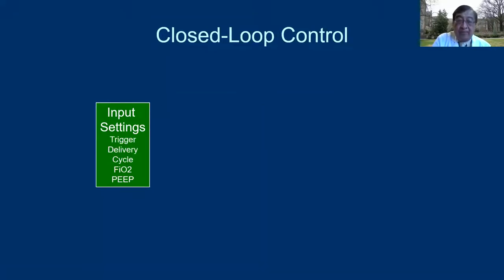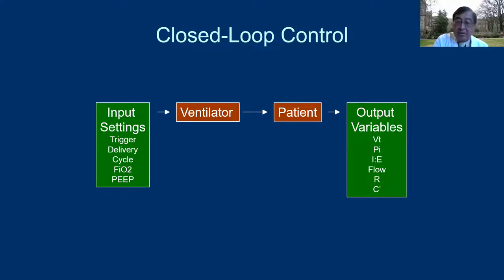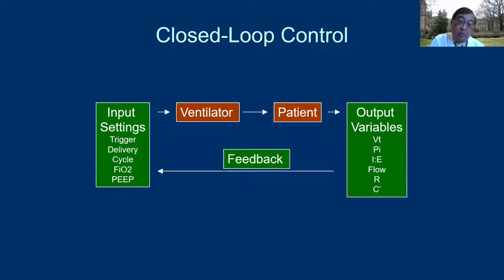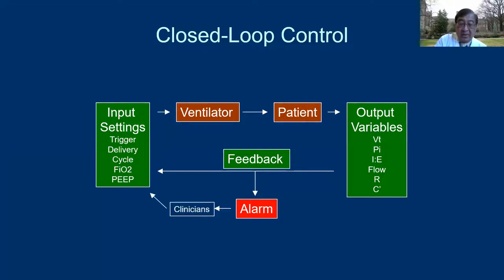Then there is closed-loop control. You still input settings, but for advanced closed-loop modes, it's not really tidal volume or rate — you input minute ventilation. Some of the output variables feed back to the ventilator, creating a feedback loop. This loop continues to run until at some point it cannot — for example, the tidal volume just cannot be decreased anymore. When the closed-loop control alarms, usually something bad has happened, so this alarm should not just be silenced.